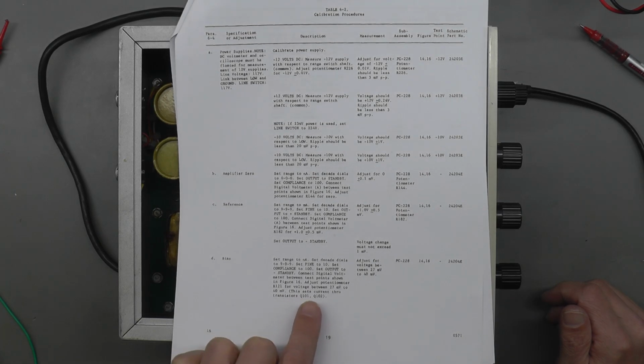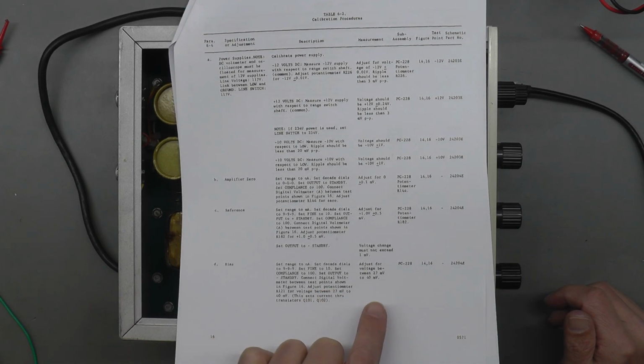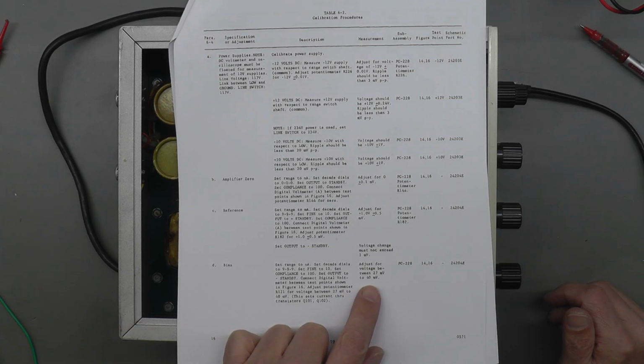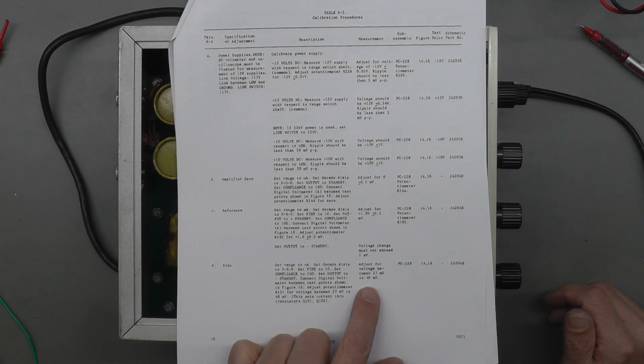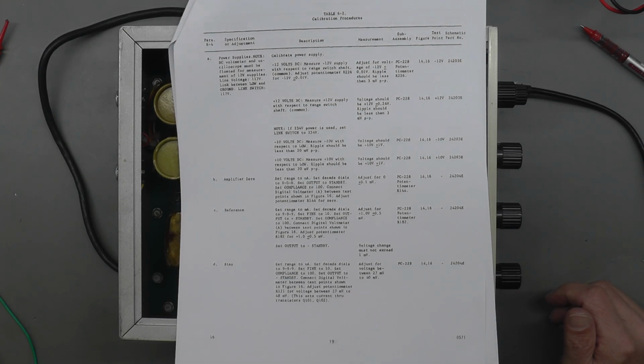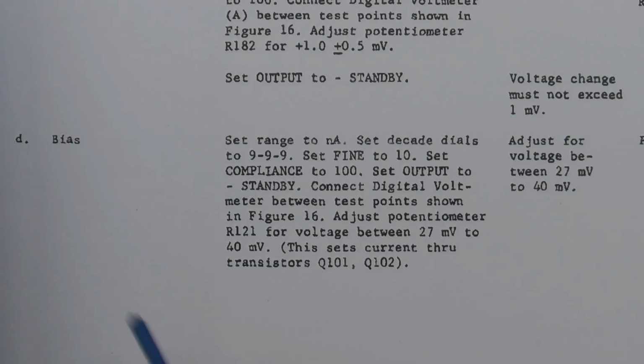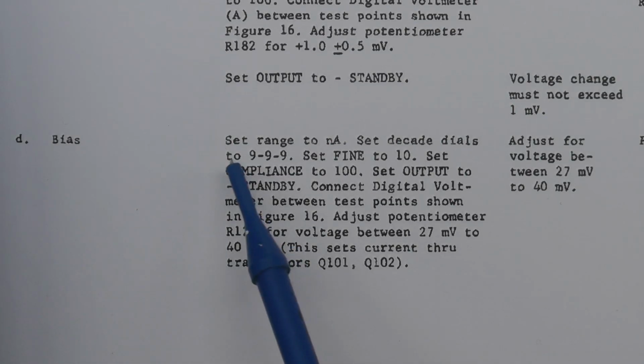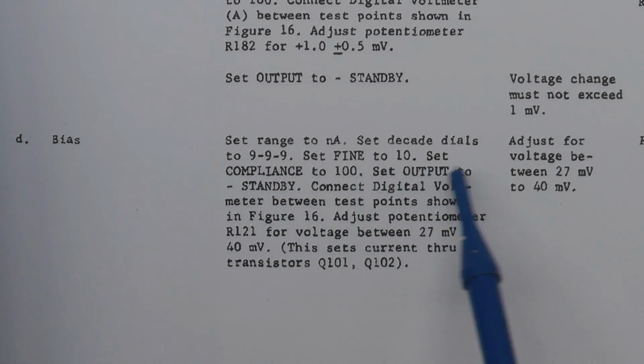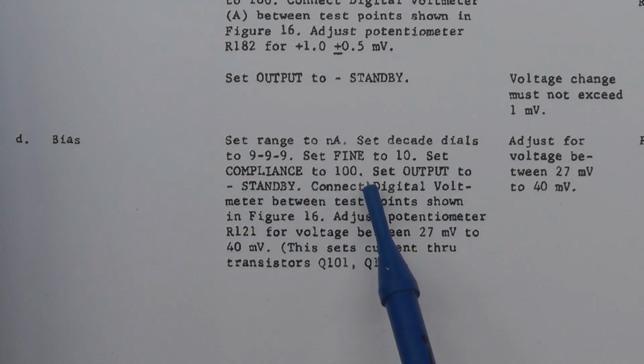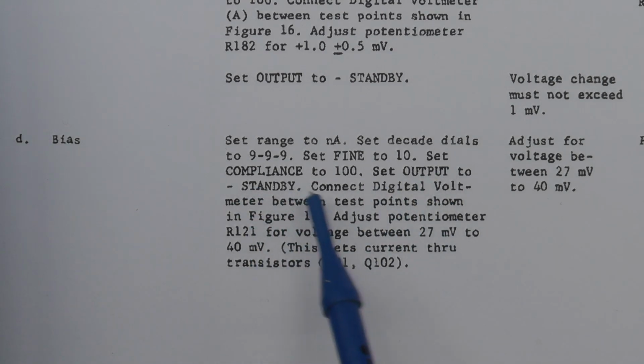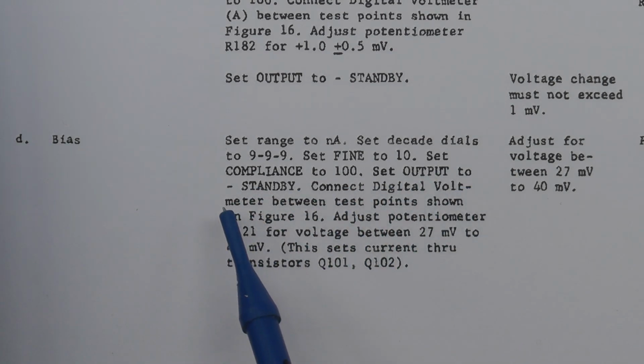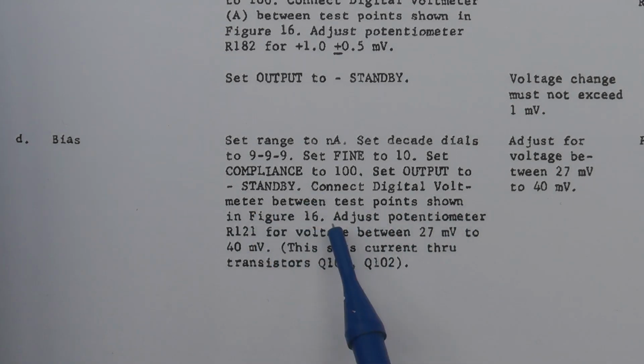The test points you're meant to test across are supposed to give a voltage of between 27 millivolts and 40 millivolts. Well, I was getting 4 volts, way off. So let me hook that up once again, and let's double check that before we go down onto the schematic. So here it is, section D, bias - set the range to nanoamps, set the decade dials to 999, set the fine control to 10, set the compliance voltage to 100, set the output to negative standby, and connect a voltmeter up as shown on figure 16.